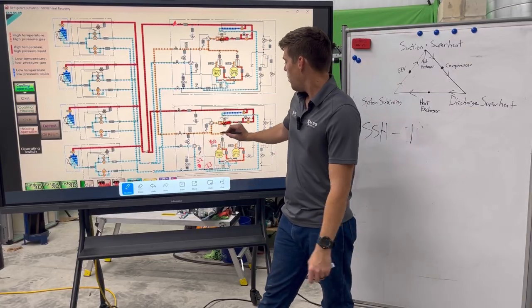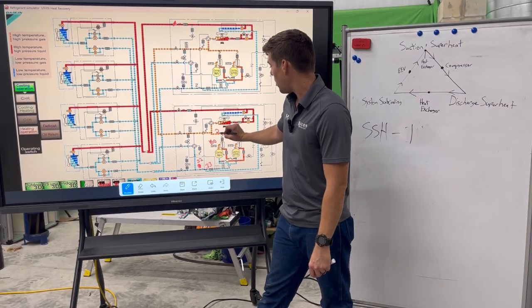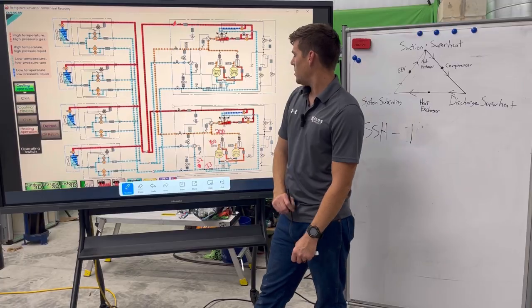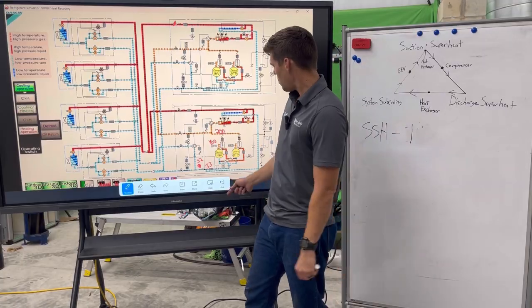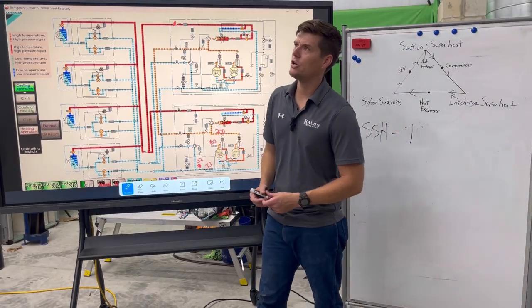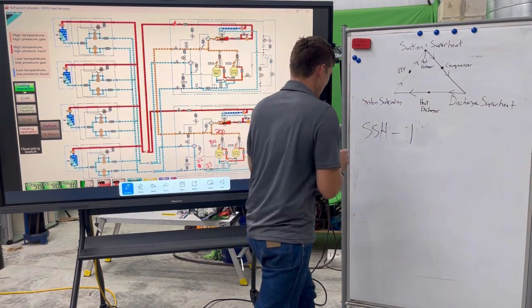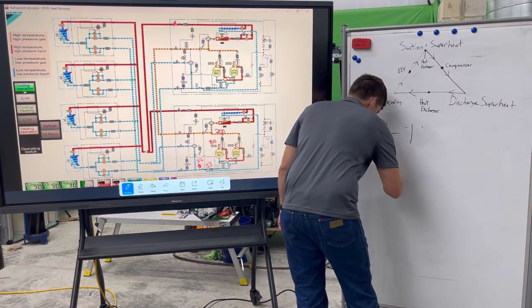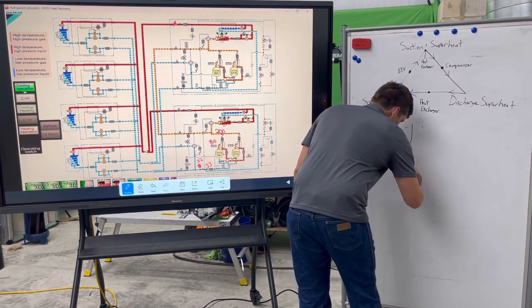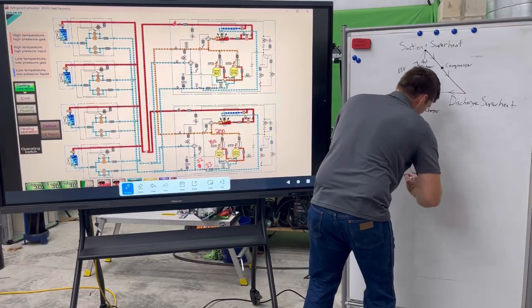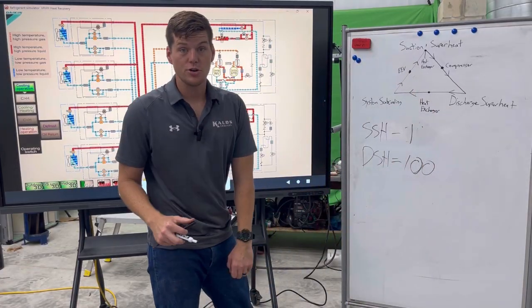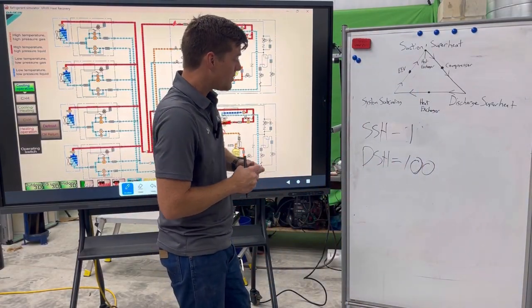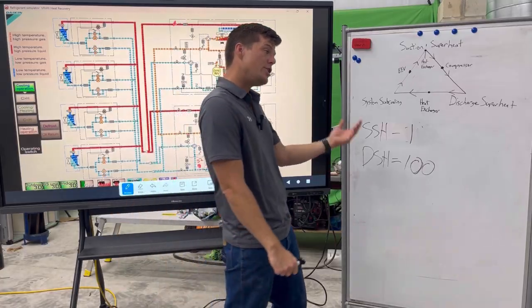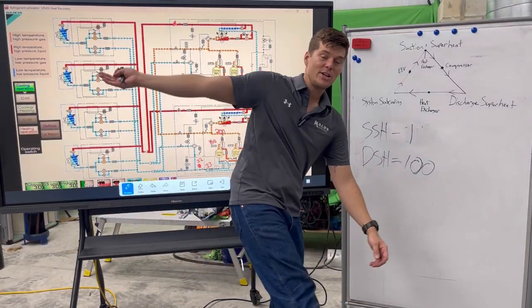Why do I need to know that? Well, because my line coming off this unit is, let's say, 200 degrees. Well, I take my saturation temperature and I do the math, and that math would be DSH equals what? 100. There we go. Yes. That's a high discharge superheat. I know that my normal range for discharge superheat is anywhere between 32 degrees and 72 degrees.